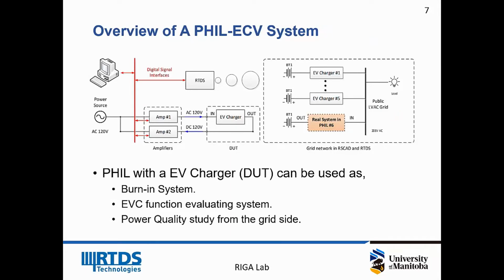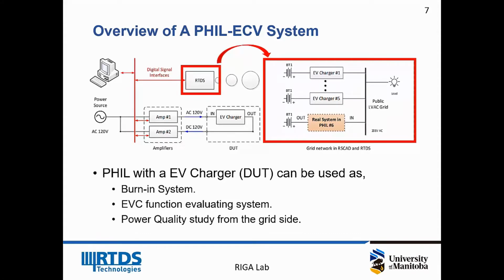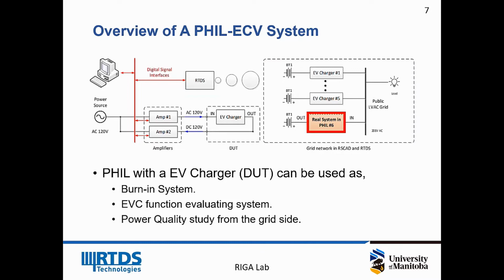If we want to connect a commercial EV charger to a simulated environment, we need an RTDS, and we should model the grid, the load, and the battery in the software in the RTDS. But the EV charger is modeled as a black box in the software. On the hardware side, the EV charger connects to 2 amplifiers. They emulate the battery and the grid. The voltage values of the emulators follow the simulated values in the software. It means the hardware and the software are exchanging information. The EV charger is running at full power, and the EV charger is thinking it is charging a battery and sourcing power from the grid.